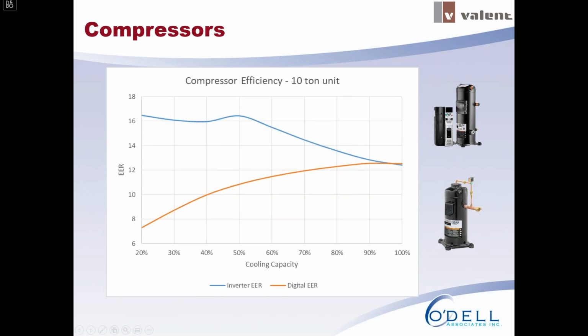You're probably going to be wanting to go with an inverter scroll. So this graph here shows a comparative analysis of a digital scroll and an inverter scroll, with the blue is the inverter and orange is the digital scroll. And you'll notice that at anything less than 100% or full capacity, the inverter scroll is much more efficient than a digital scroll. So the digital is a little bit more efficient at full load, but think about how often you're going to be in that full capacity mode. Probably not too often throughout the year. You're mostly going to be in that part load condition. So you're going to reap those benefits with an inverter scroll compressor, just by all that efficiency gain with the system.